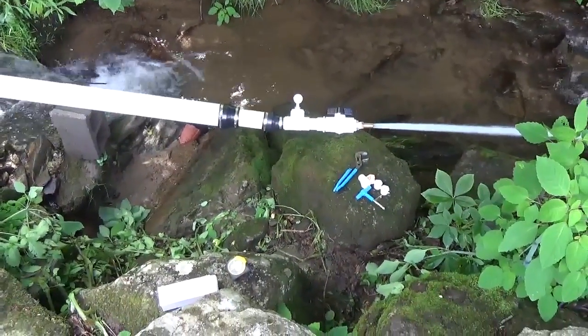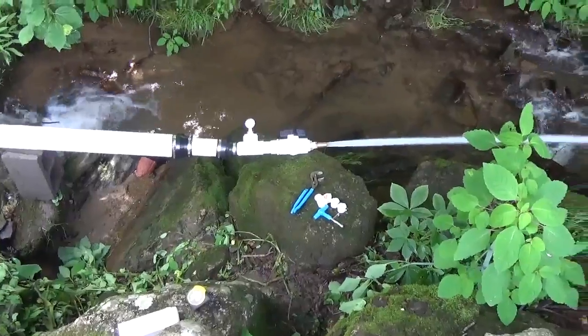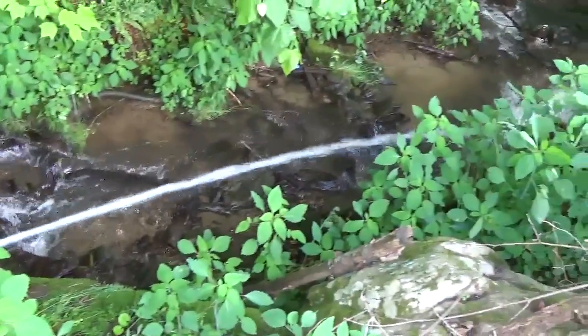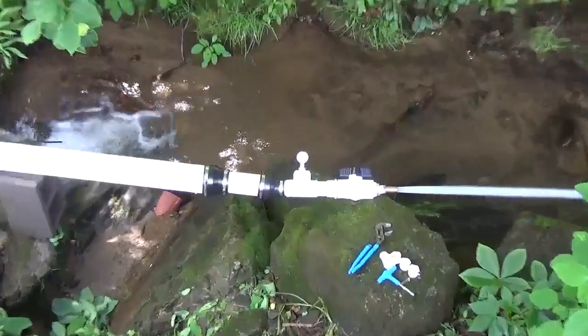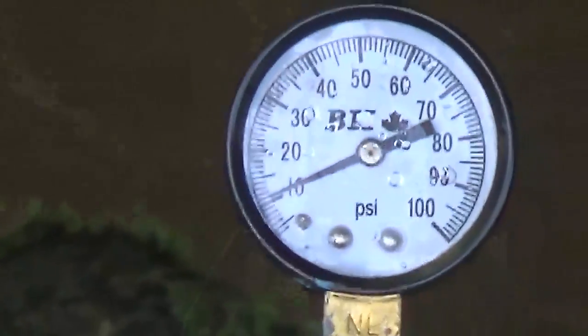We've got a 13/16th nozzle on here. We're shooting it a long ways — I would say at least 20 feet — and it should be about 11 PSI, that's where we were before. I'm going to zoom in that far. I think we're just about hitting 11 PSI.